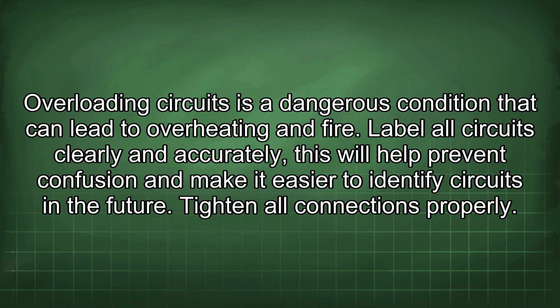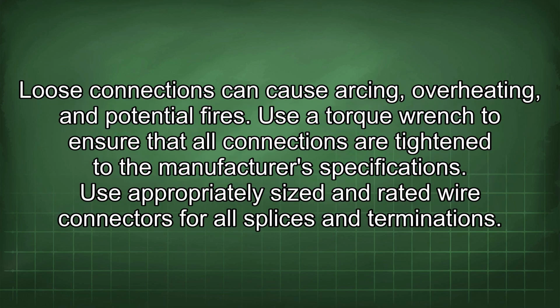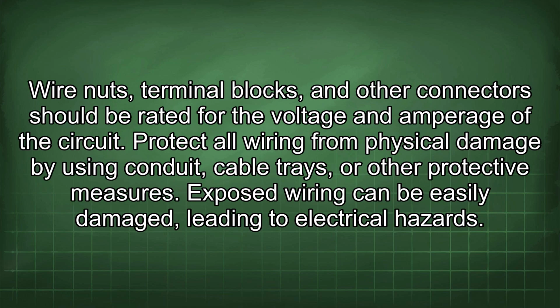Tighten all connections properly. Loose connections can cause arcing, overheating, and potential fires. Use a torque wrench to ensure that all connections are tightened to the manufacturer's specifications. Use appropriately sized and rated wire connectors for all splices and terminations. Wire nuts, terminal blocks, and other connectors should be rated for the voltage and amperage of the circuit. Protect all wiring from physical damage by using conduit, cable trays, or other protective measures. Exposed wiring can be easily damaged, leading to electrical hazards.